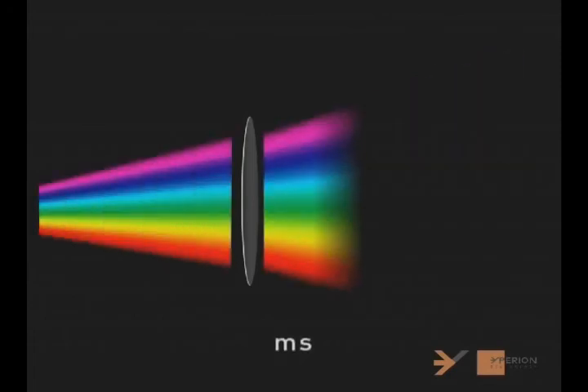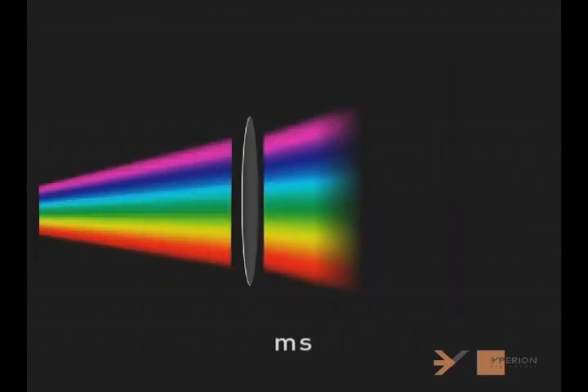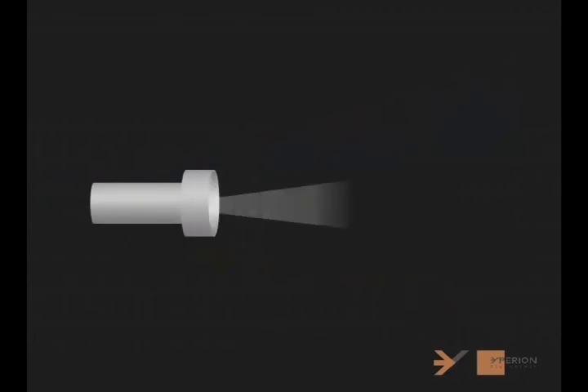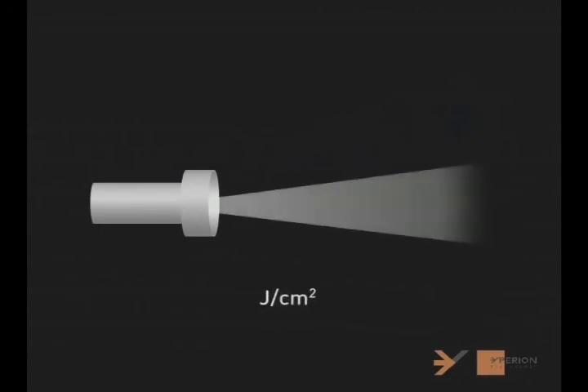Pulsed light is emitted in bursts that last a few milliseconds, called pulses. The pulse duration must be adjustable. The energy from the light beam is called fluence, and it is measured in joules per square centimeter.